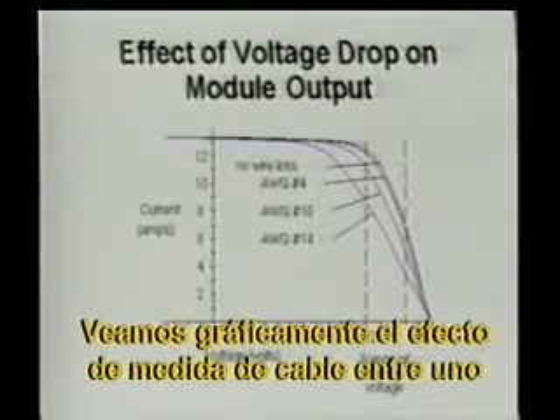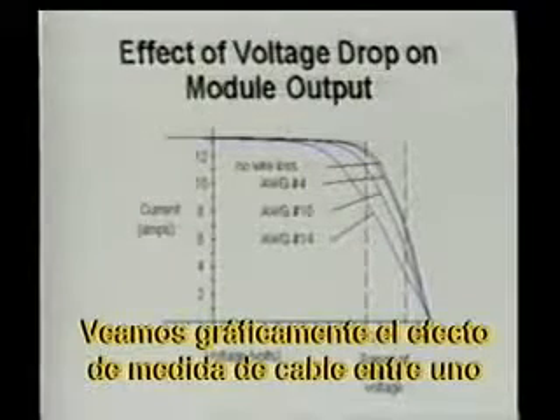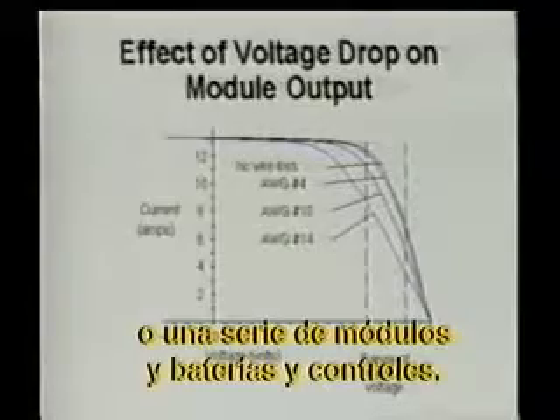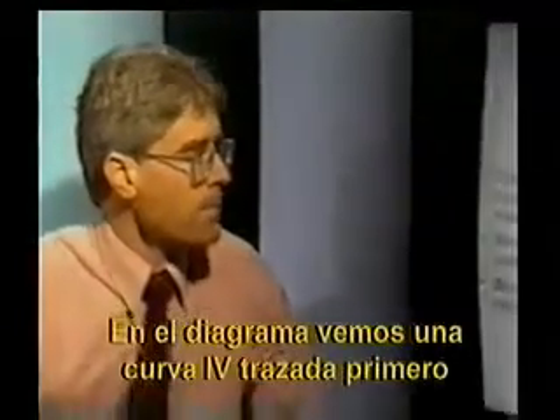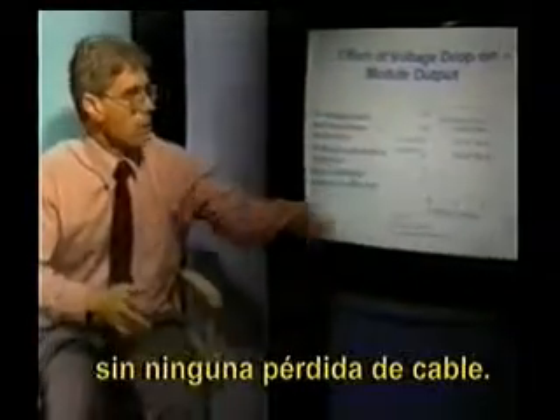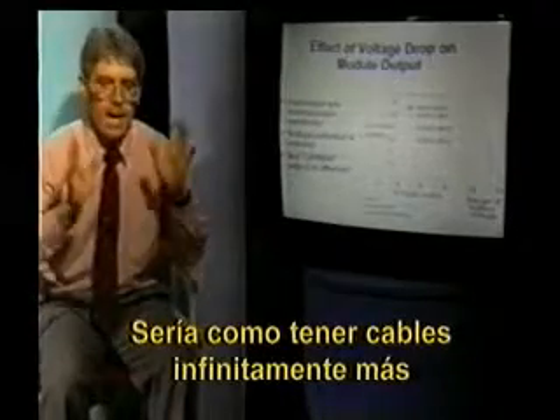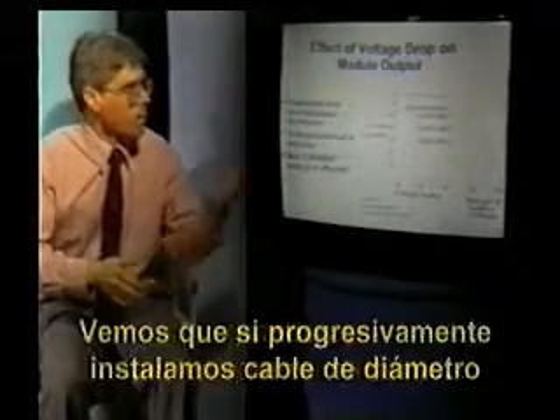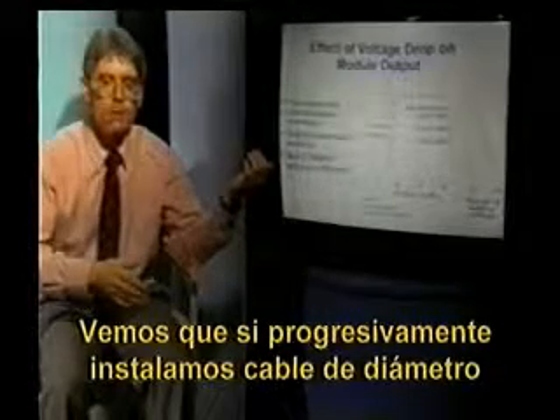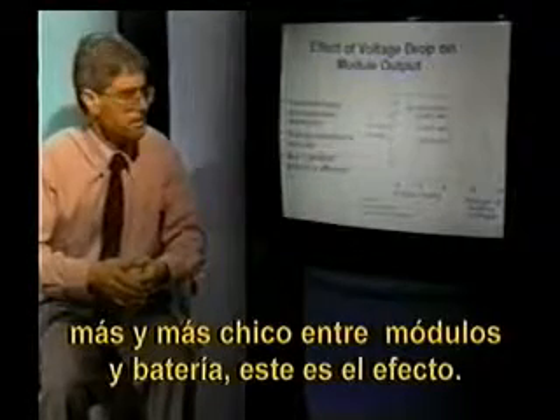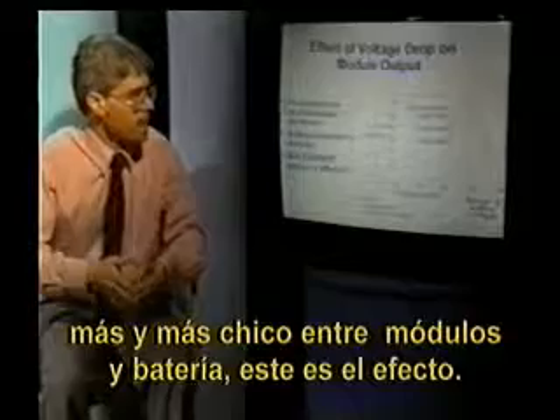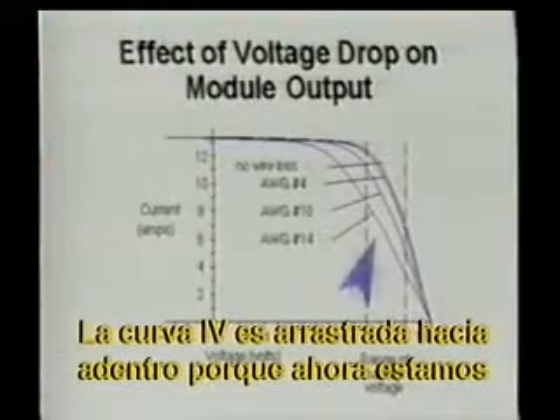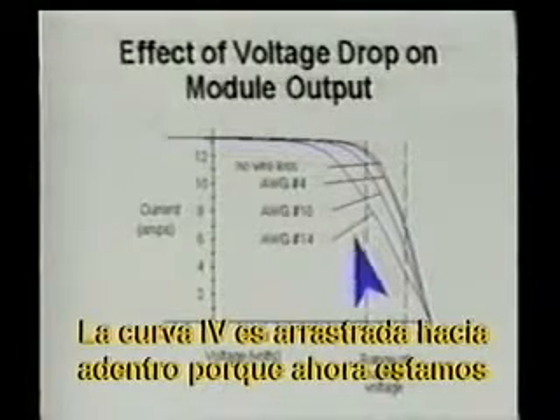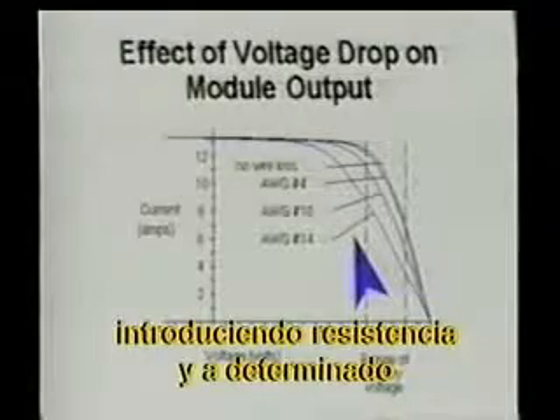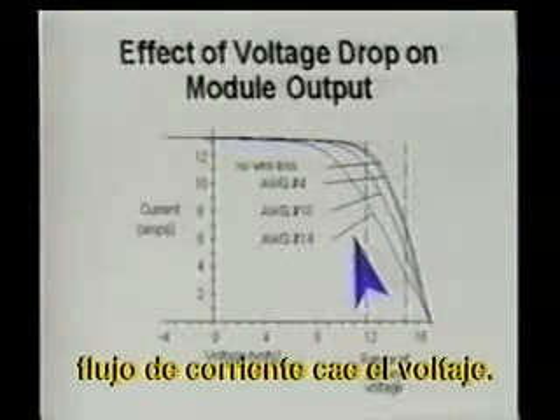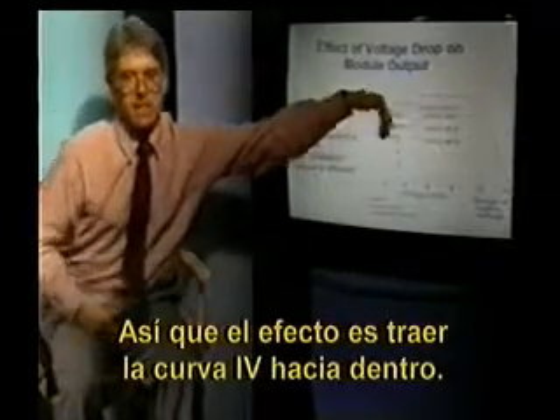Let's take a look graphically at the effect of wire size between a module or a series of modules and batteries and controls. In our diagram, we look at an IV curve first drawn with no wire losses at all. That would be as if we had infinitely large or perfectly sized wires. Now, what we can look at is if we install progressively smaller and smaller diameter, smaller gauge wire between our modules and our battery, the effect is as shown. The IV curve effectively is dragged inwards because we're now introducing resistance. At a certain current flow, we have a voltage drop. At a higher current flow, we have a higher voltage drop. So the effect is to bring the IV curve in, to slant it inward.